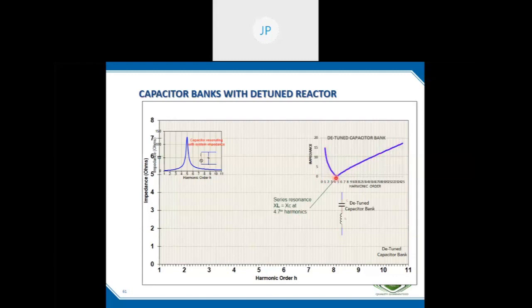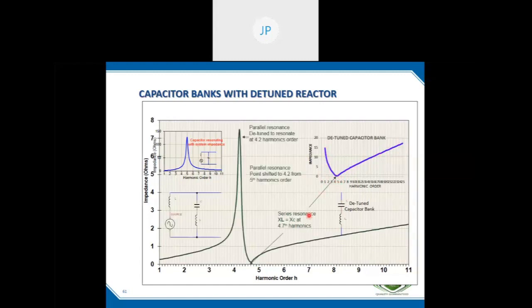In the capacitive region, to have a resonance we need a capacitor. Further, the resonance point will be only at a lower frequency than 4.7. This is the wave shape of the frequency scan of the system plus the detuned reactor, and it has two resonances. One is the series resonance, represented here, and the parallel resonance point is here. So what happened here? The peak resonating point is shifted from 5 to 4.2.